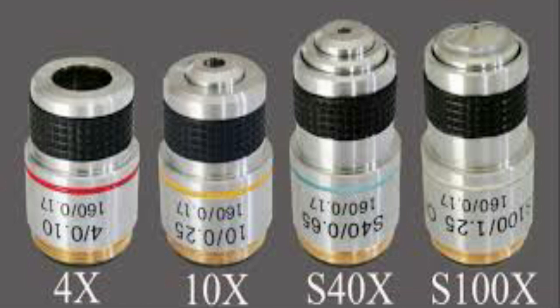Usually you will find three or four objective lenses on a microscope — almost always 4x, 10x, 40x, and 100x powers. When coupled with the 10x eyepiece lens, you get total magnifications of 40x, 100x, 400x, and 1000x just by combining two lenses. The condenser lens is used to focus light onto the specimen and is most useful at the highest powers, 400x and above.